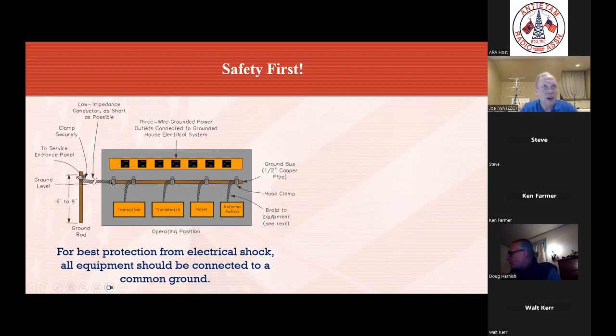And then from there, you want to have a good quality conductor going out to a grounding rod. Again, something that you can pick up at Walmart, Lowe's, or Home Depot. They're typically 6 to 8 feet deep or 8 feet long. And quite literally, you pound them into the ground and you connect your station to them. And what that does is it creates a neutral reference point for all the equipment in your station.